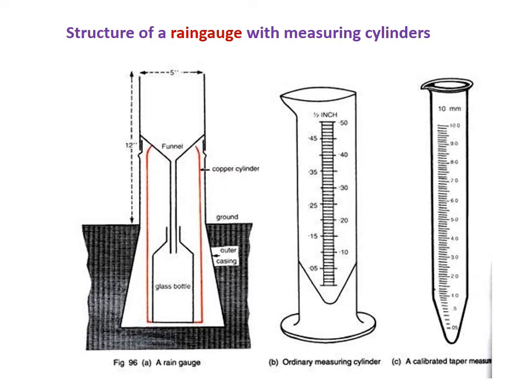For example, in India we use 200 square centimeters for the mouth of the funnel, whereas in the UK they use 450 square centimeters. That is a much larger funnel than what we use. So the rain gauges will need to be calibrated by the India Meteorological Department if you want to present that data for the public.